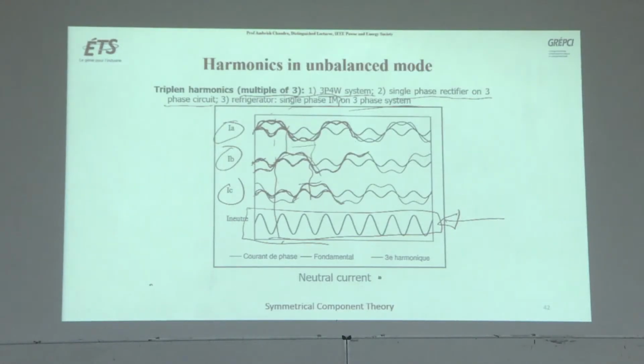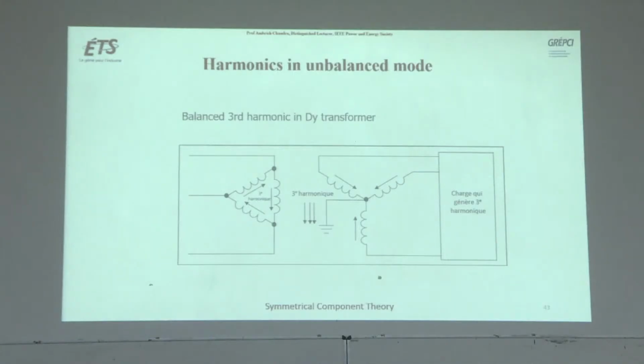So the engineer in a plant should be very careful what kind of load you are having and what kinds of harmonics are being generated. If there are zero sequence harmonics, they may flow in the neutral wire, and sometimes they overload the neutral wire and heat it up, and in very worst cases they may even burn the neutral. So this is very important about the triplen harmonic. Many times we will see that you have a non-linear load which is generating third harmonic. So the third harmonic is trapped in delta. They will not come out and will not pollute the network if you have a delta here. Okay, that we will see soon.